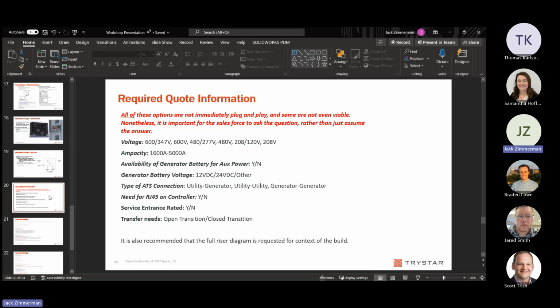What about you, curiosity Chris? That would probably be handled more on the electrical review side, because I'm curious about breaker stuff—are these inherently LSIG breakers since they have bell alarm as part of the design? Well, they're not inherently that—there are two separate alarms. That's a ground fault alarm, and the bell alarm is just an indication contact.